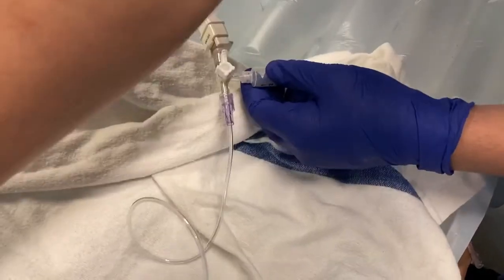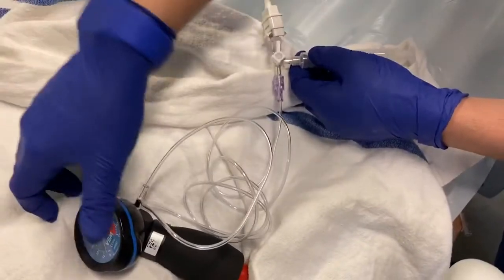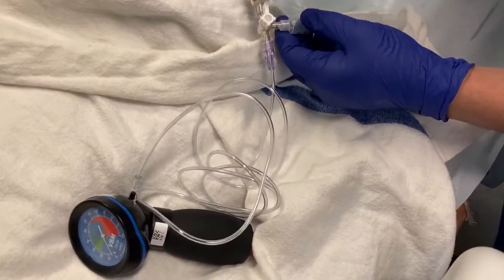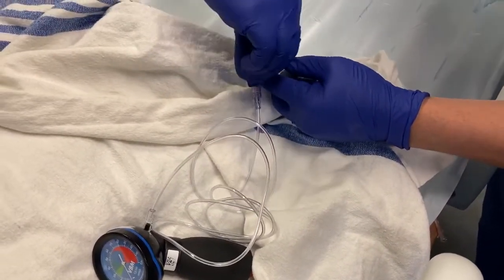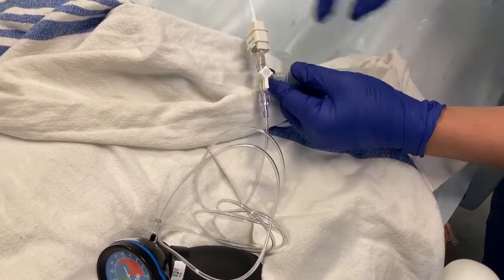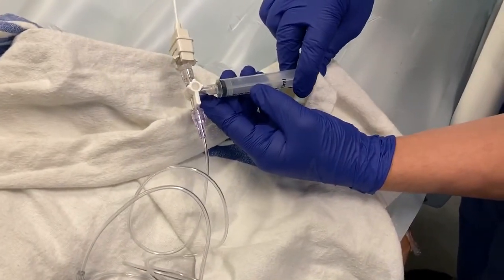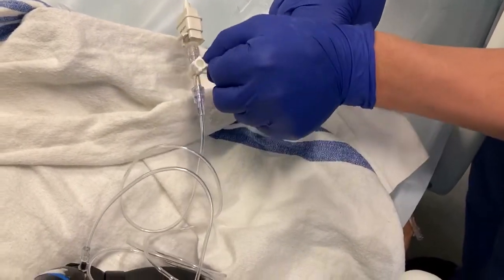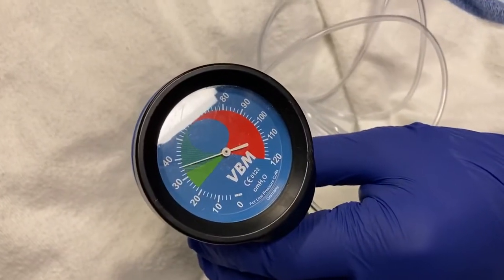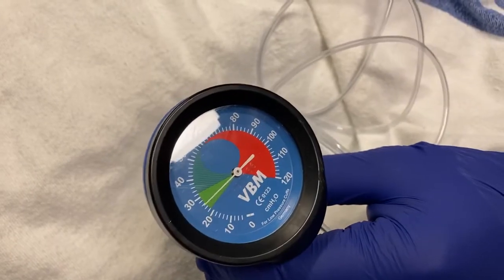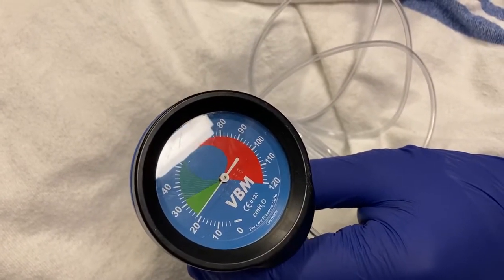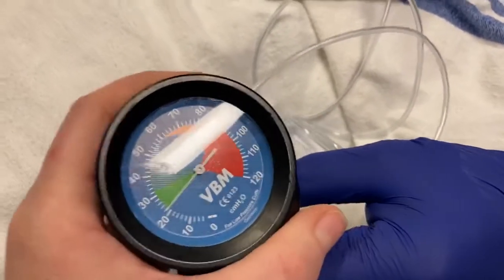And then at this point, just to confirm that your pressure is going the right way, I'm going to open to the patient over here and push that 3 cc's into the balloon. Then at this point, you want to open to your transducer, and you're going to start to get a read. It will start high because the pressure is moving, and then it will stabilize and you'll see what your esophageal pressure is.